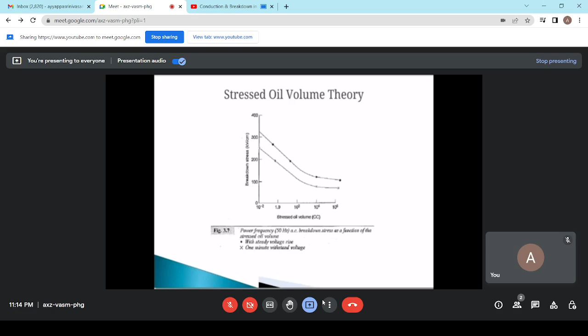According to this theory, the breakdown strength is inversely proportional to the stressed oil volume. Here we have shown the power frequency AC breakdown stress as a function of the stressed oil volume. The breakdown voltage is highly influenced by the gas content in the oil, the viscosity of the oil, and the presence of other impurities. These being uniformly distributed, an increase in the stressed oil volume results in a reduction in the breakdown voltage, and the variation of breakdown stress with stressed oil volume is again shown in the image.